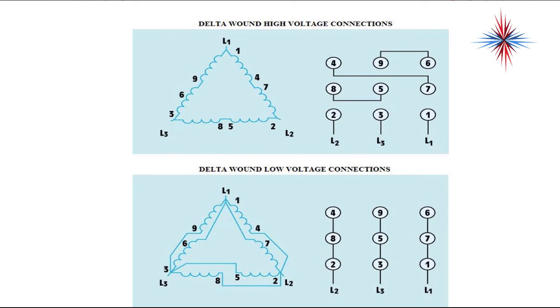So, it's very important to look at the label because you might have to reconfigure the motor or you might have extra leads that you need to know what to do with. Normally, these leads either have a little tag on it with a number on it or they're going to be different colors. Just make sure you get the right one in the right position because if you get it wrong, you can actually burn out a motor winding. And that means that your company or you has to replace that motor.